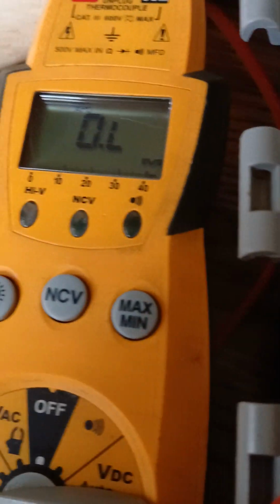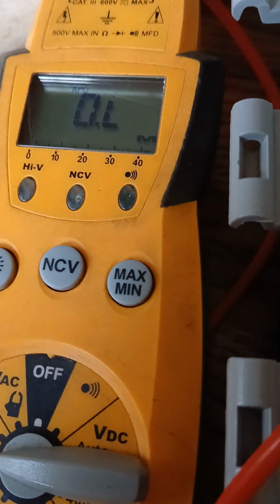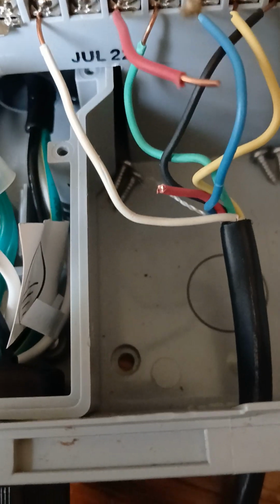Between 20 and 60 would indicate the valve was good. So we know the break is here. The OL tells us that we may have a break, and we can clearly see the break where the wire is separated between this wire and this particular wire.